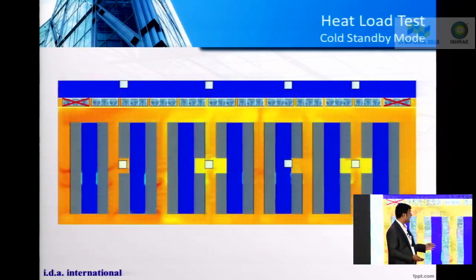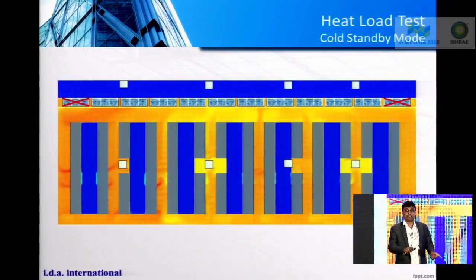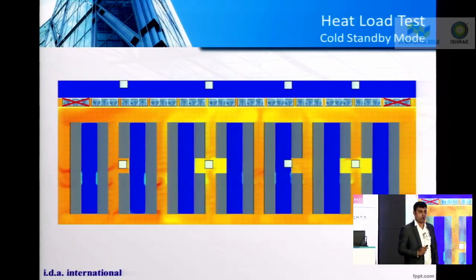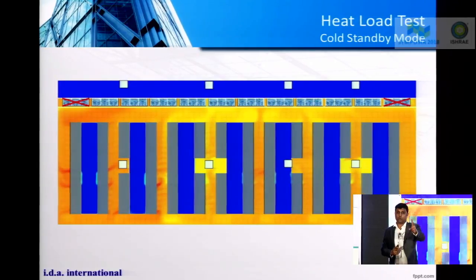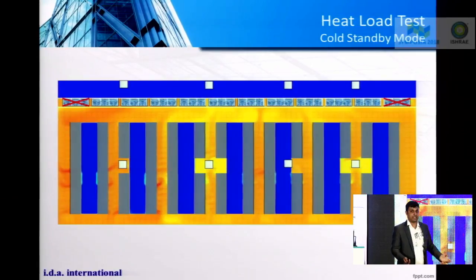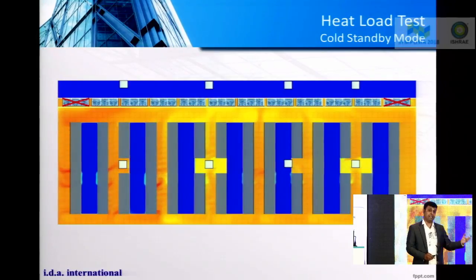Now, the second thing I can do is simulate the same thing in a cold standby mode. If I have designed my data hall with N+2 configuration, I can choose any 2 CRAC units and put them into standby mode. So if I have 12 units, 2 units will be on standby and 10 units would be running. And I can create multiple scenarios here.